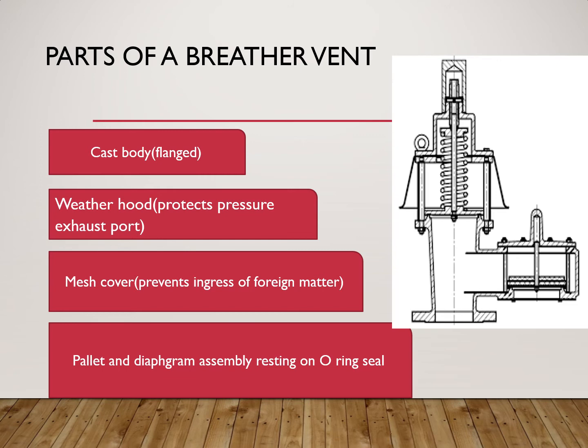The breather vent may be connected to the vent system, meaning other devices such as scrubbers can be connected. The pressure and vacuum sides of the valve have a pallet and diaphragm assembly resting on an o-ring seal to prevent leakage. The weight of the pallet pushes the diaphragm against a seat to keep it closed.